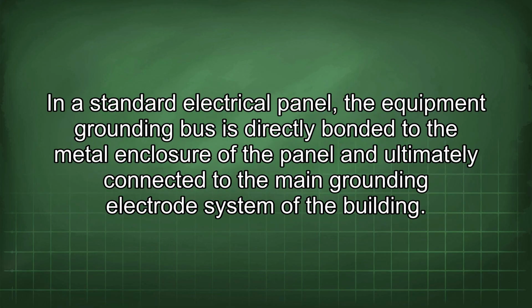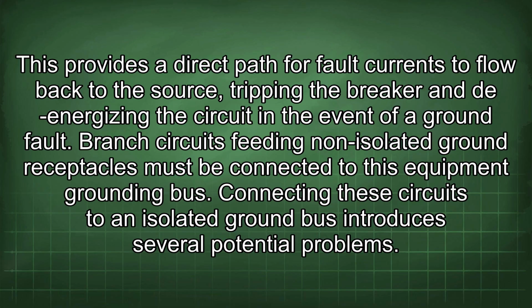In a standard electrical panel, the equipment grounding bus is directly bonded to the metal enclosure of the panel and ultimately connected to the main grounding electrode system of the building. This provides a direct path for fault currents to flow back to the source, tripping the breaker and de-energizing the circuit in the event of a ground fault. Branch circuits feeding non-isolated ground receptacles must be connected to this equipment grounding bus.